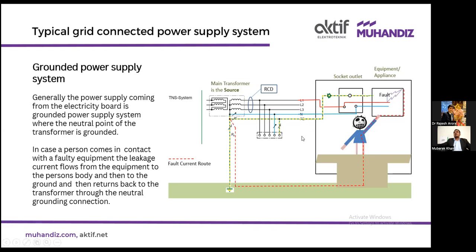Now, this is one scenario where your leakage current will cause a blackout. Now, suppose this earth conductor, which flows from the equipment to the body, does not have perfect integrity and is broken somewhere. In that scenario, what will happen? The current will not pass through the body, but rather it will try to find some other path.